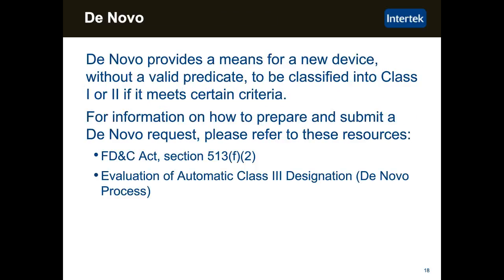A more recent process in order to get your product to market is the de novo process. And de novo provides a means for a new device where there is no valid predicate to be classified into Class 1 or Class 2 if it meets certain criteria. For more information on how to prepare and submit a de novo request, you can refer to the resources listed on the slide. So typically a device would automatically be Class 3 if there was no predicate.